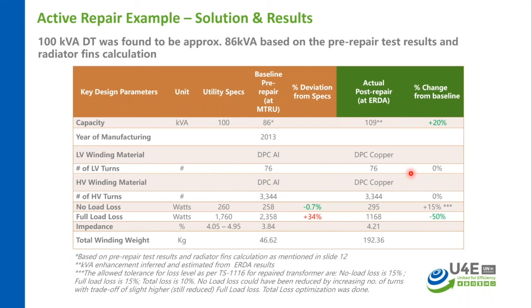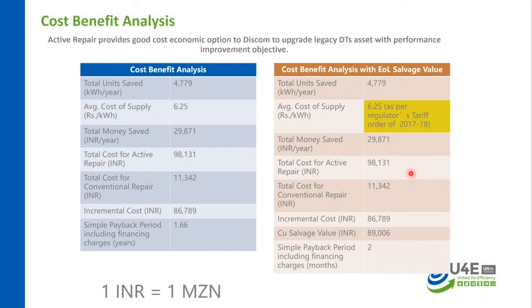Now the utility specification provides it for the 100 kVA, but they were actually using 86 kVA. As a result of that, this transformer failed 2 times because of the overloading. And then this transformer also had the losses higher to the tune of 34% compared to the specification. So after redesigning of this transformer at the time of repair, the kVA capacity was enhanced by 20% and the losses were reduced by 50%. So the economic payback period for these transformers was seen as 1.66 year just by redesigning at the time of repair. The losses were reduced considerably.